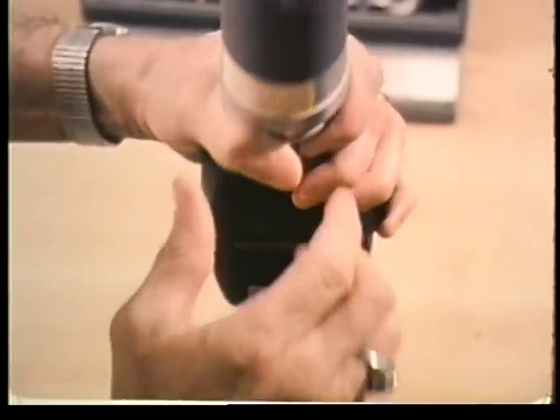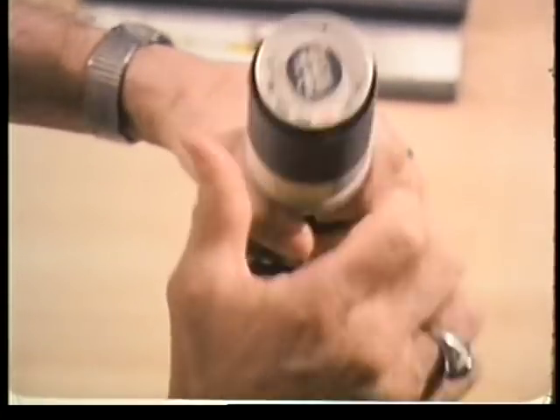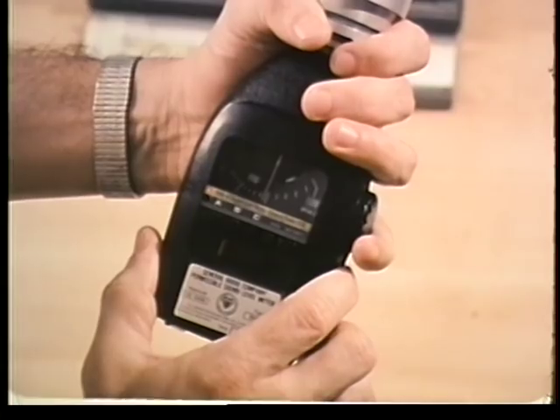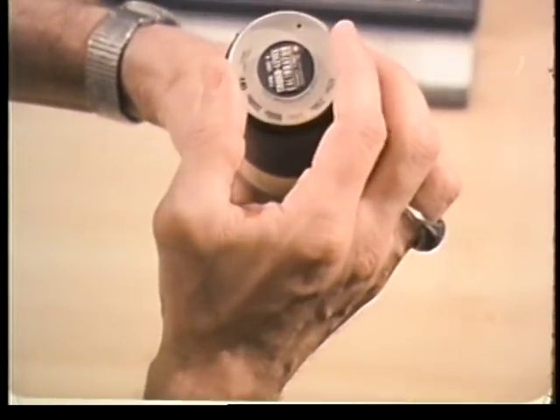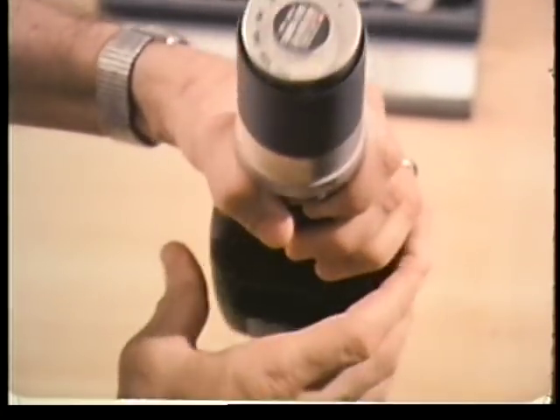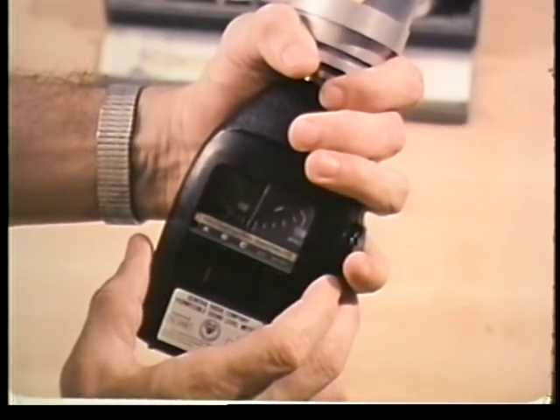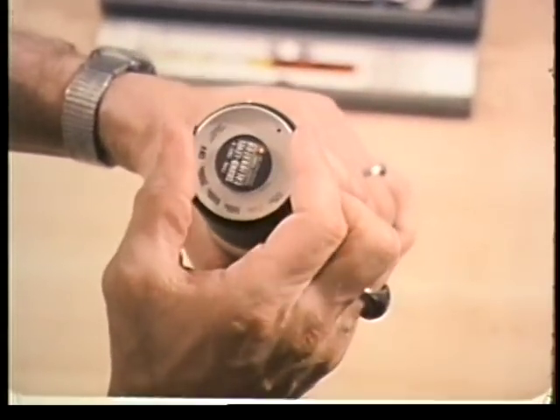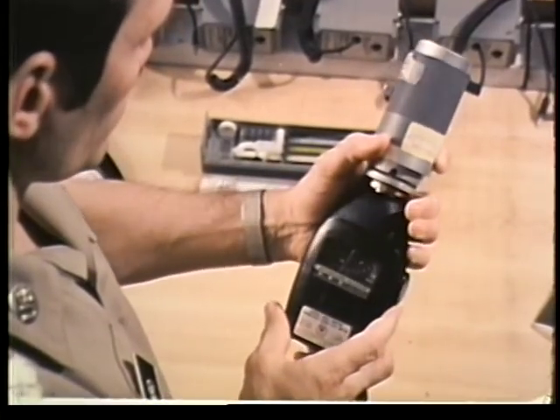During the survey, the meter will be set on the A scale, slow response. The A scale is designed to hear on the same curve as the human ear, and OSHA regulations require measurements to be taken on this scale and slow response.